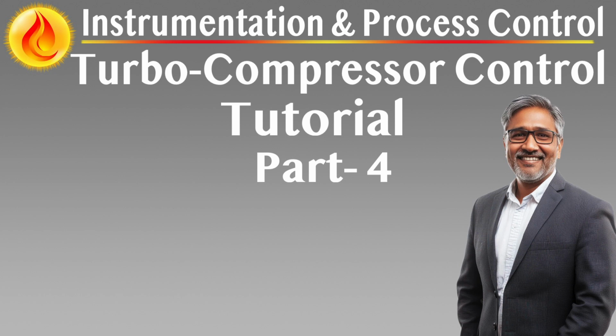Final termination to UCPs and external systems is completed by others based on standard interface definitions. Instrument wiring is laid out to minimize electrical noise and crosstalk, maintain segregation between analog, digital, and high-power circuits, and support loop checks and commissioning activities without disruption. Commissioning and testing provisions. Loop testing and verification. All instrumentation loops are tested for continuity, range calibration, response time, alarm and trip functionality.